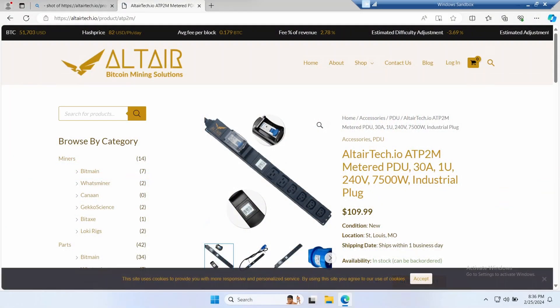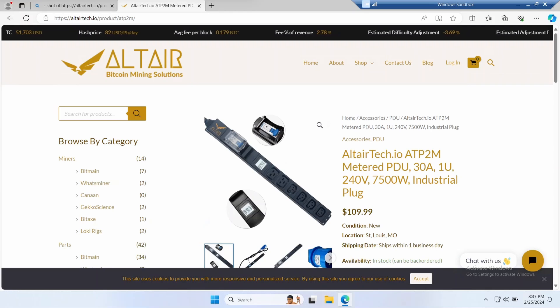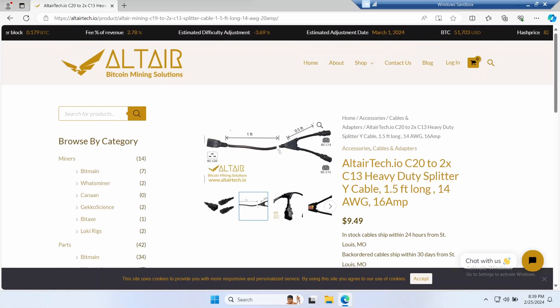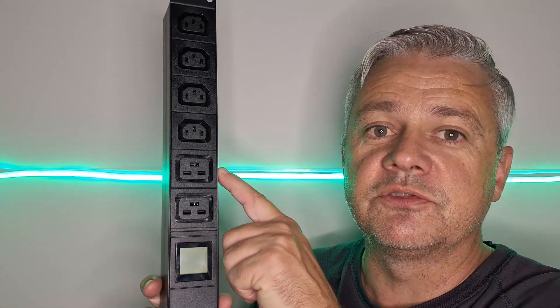Now that we have our 30 or 32 amp circuit with the IEC 60309 socket, we need a PDU to give us C13 and C19 plugs. This is not sponsored, but I personally like the Altair Tech PDUs. They are well priced and can include metering so you can claim the power you use as a tax expense. Their PDUs have just the right amount of outlets for crypto mining and are very nice and small. Because an S19 has a pair of C14 power sockets, I like to use a C20 to dual C13 power adapter. Altair Tech sell these as well, and because the PDU has a pair of C19 outlets, you can plug two ASICs directly into it.